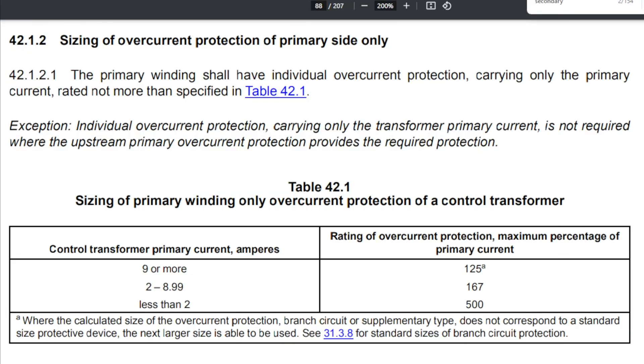Let me show you why. In UL 508A, if we go to section 42.1.2 — Sizing of Overcurrent Protection for Primary Side Only — it says: for control transformer primary current of 9 amps or more, you're going to be at 125% of your primary current; 2 to 8.99 amps, you'll be at 167%; and less than 2 amps, you're going to be at 500%.